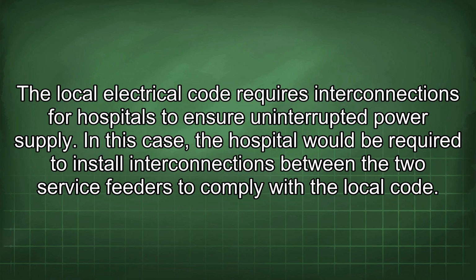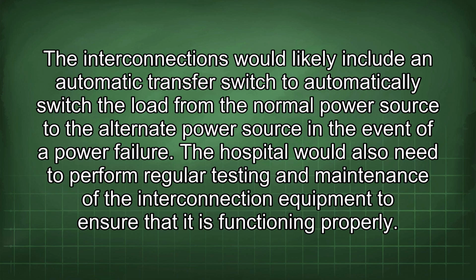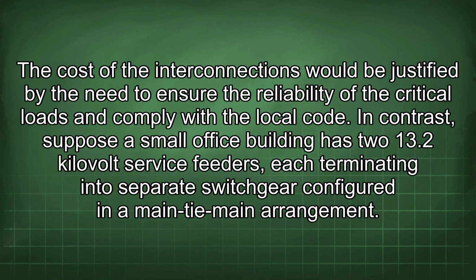The interconnections would likely include an automatic transfer switch to automatically switch the load from the normal power source to the alternate power source in the event of a power failure. The hospital would also need to perform regular testing and maintenance of the interconnection equipment to ensure that it is functioning properly. The cost of the interconnections would be justified by the need to ensure the reliability of the critical loads and comply with the local code.